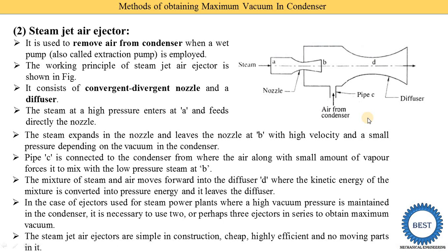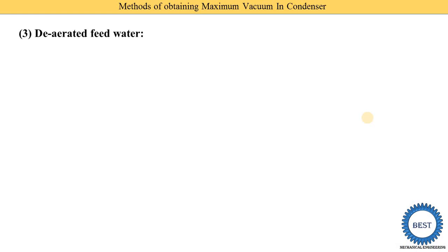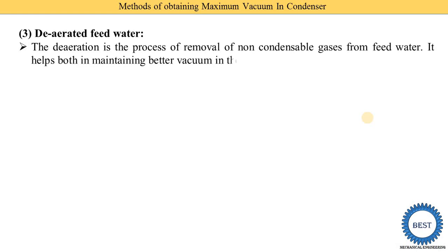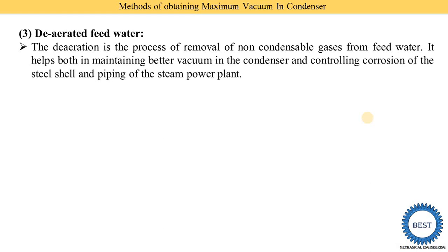The third method is deaerated feed water. Deaeration is the process of removal of non-condensable gases from the feed water. We use already-treated feed water from which the non-condensable gases have been removed before it is used in the condenser. This helps in maintaining better vacuum in the condenser and controlling the corrosion of the steel shell and piping of the steam power plant.